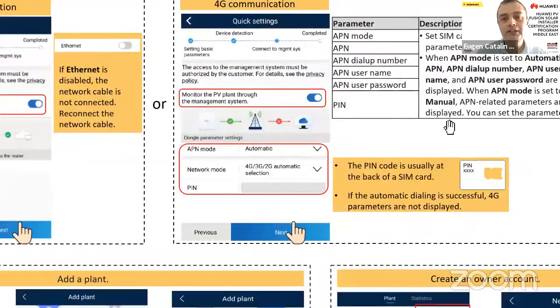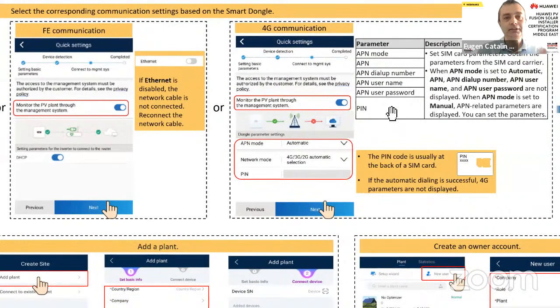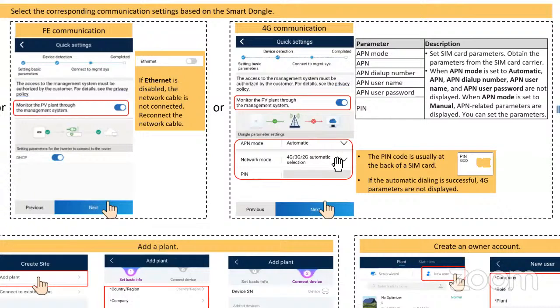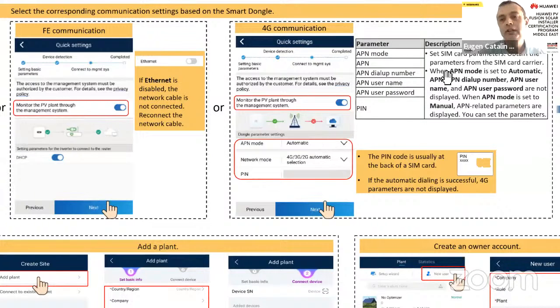If we use a 4G dongle, the inverter will auto-detect the 4G communication in this step. The 4G connection can be automatic or manual. If I set manual, I need to set all of this: APN mode, APN number, username, password, PIN, whatever. And I need to know all of this from the operator, or from the paper of the SIM card, from somewhere. I need to have these details. If I don't know, I will put automatic. Of course, before connecting the 4G dongle, we need to test the SIM card, yes, to work. We need to test whether the 4G works or not.